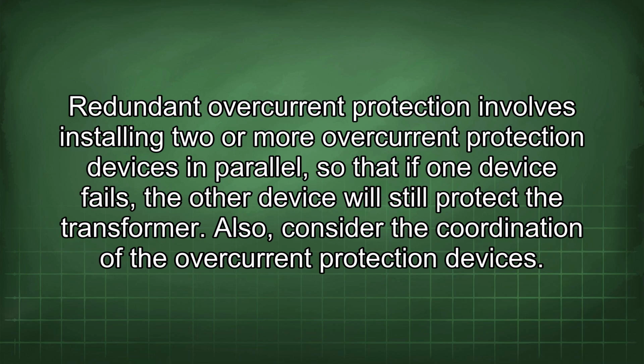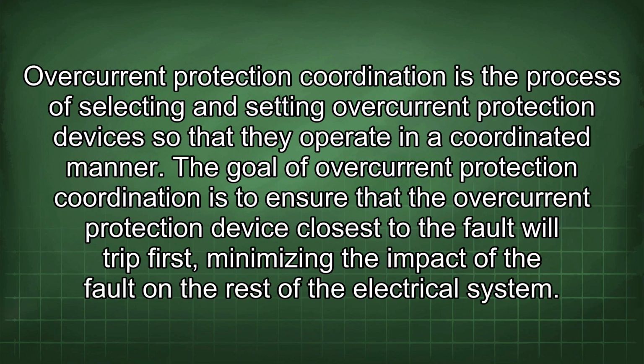Also, consider the coordination of the overcurrent protection devices. Overcurrent protection coordination is the process of selecting and setting overcurrent protection devices so that they operate in a coordinated manner. The goal of overcurrent protection coordination is to ensure that the overcurrent protection device closest to the fault will trip first, minimizing the impact of the fault on the rest of the electrical system.